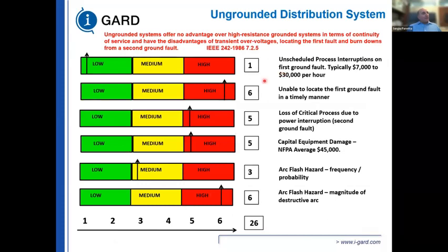When we put the meter to it, unscheduled process interruption is very low. You should not have any interruption in your power system with an ungrounded system, because the only thing you do is detect the presence of a ground fault. You can't find where that ground fault is, because in order to find it, you have to have power interruptions and trace the fault downstream. Loss of critical processes occurs on the second ground fault, because you don't know where the first ground fault is. Electricians tend not to worry about where the ground fault is because they can't find it. Chances are you're going to get a second ground fault, which can come from deteriorating insulation in other areas, or a timed second ground fault.